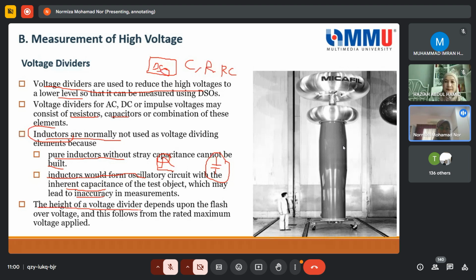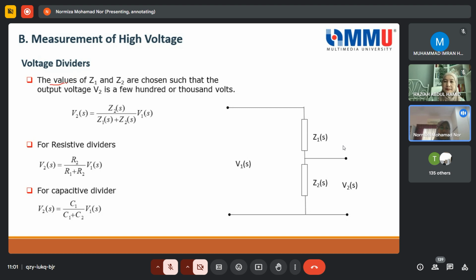The height of the voltage divider depends upon the flashover voltage. The higher the voltage, normally you would see that the higher it is from the ground, because this also needs to provide the clearance. So in general, the principle is that the values of Z1 and Z2 are chosen such that the output voltage is a few hundred or thousand volts. It means that your V2 is the one that you measure at the DSO, and this one is the voltage applied on the equipment, like for example 100 kV.